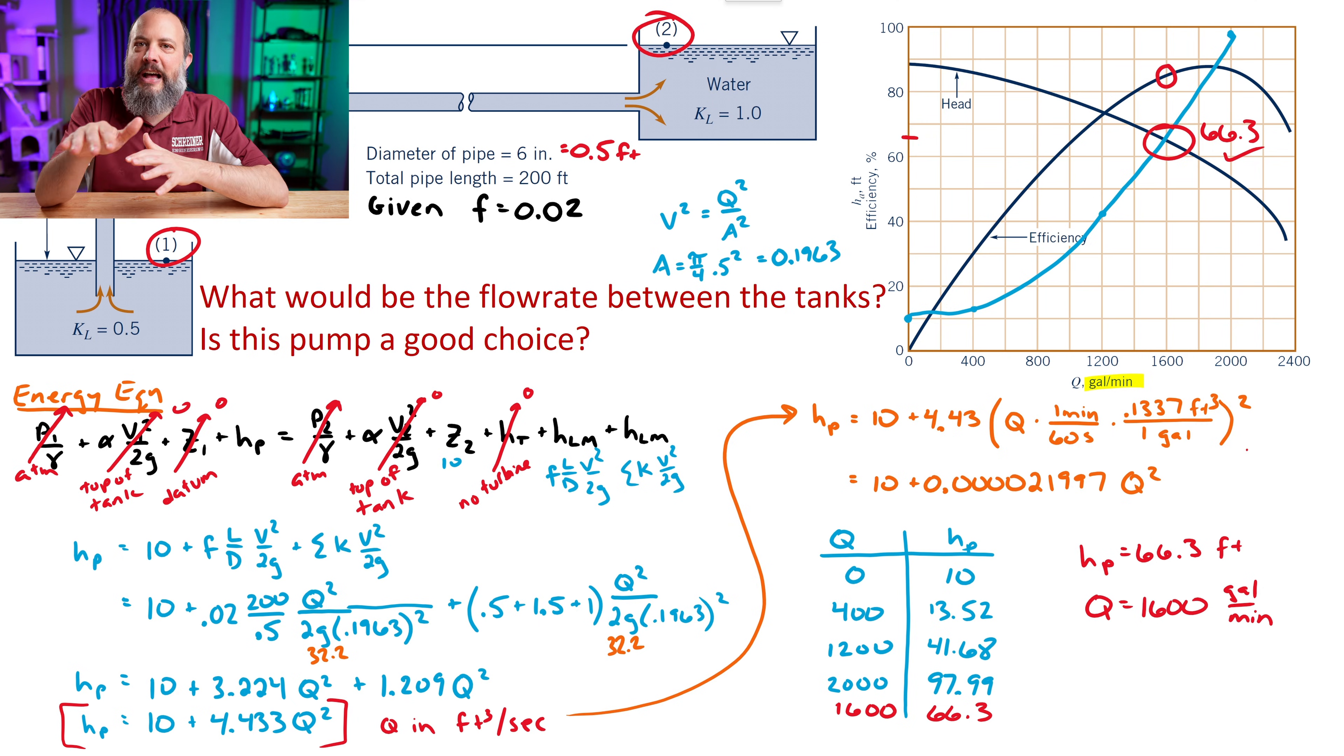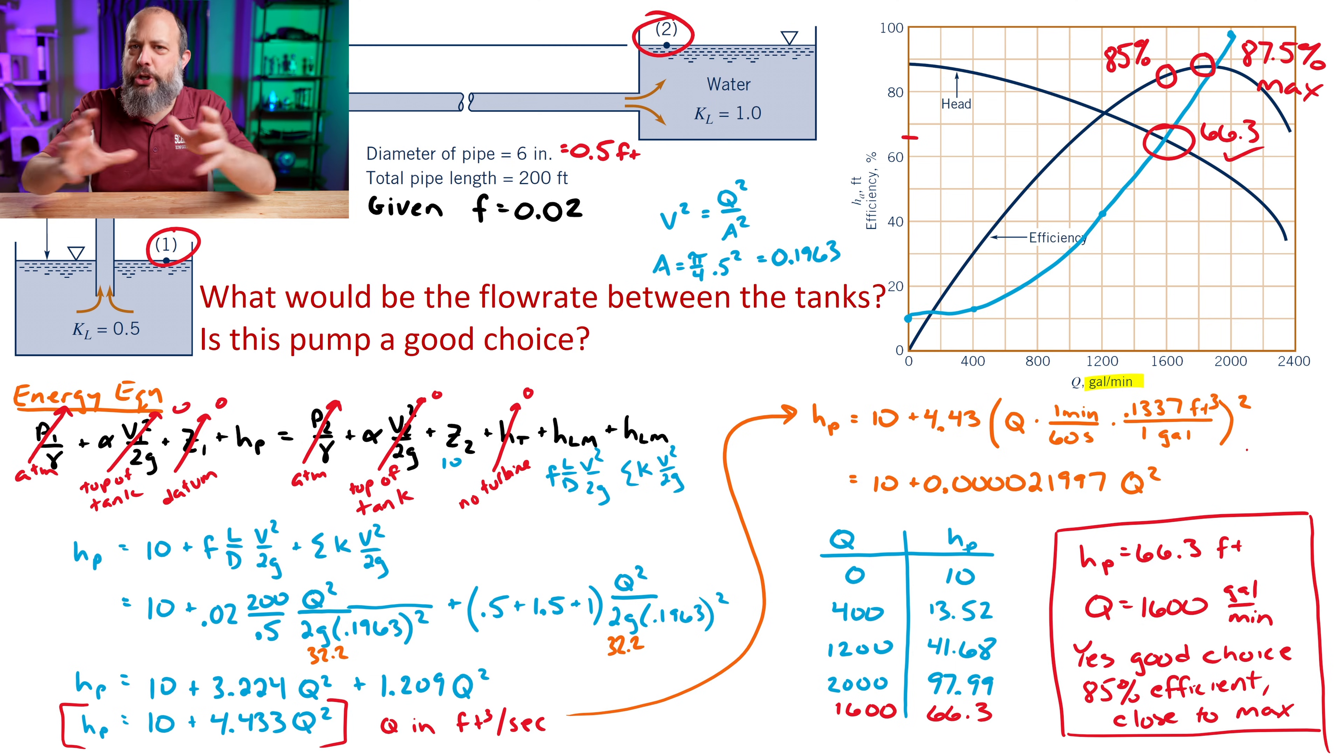But if we assume that 1,600 is a flow rate that we can work with, then this pump is a good choice. The maximum value for efficiency, we can see this peak, is right around 87%. And the flow rate we're working at is really close to that. If we go up at 1,600 gallons per minute, we're at about an 85% efficiency, which is really close to the peak. So anything between about 1,400 gallons per minute and 2,200 gallons per minute is probably a good use for this pump. Kind of in that area of the curve, all pretty close to peak efficiency, it's a good time for this pump.